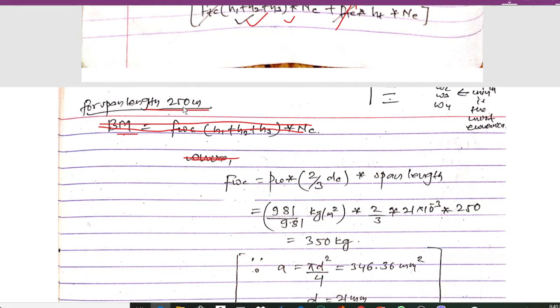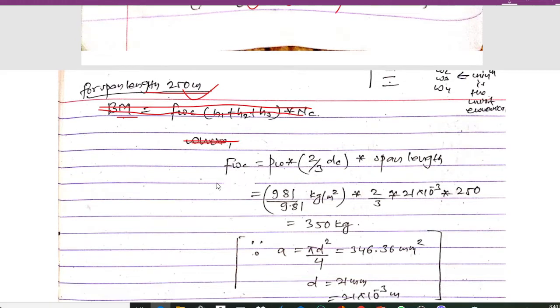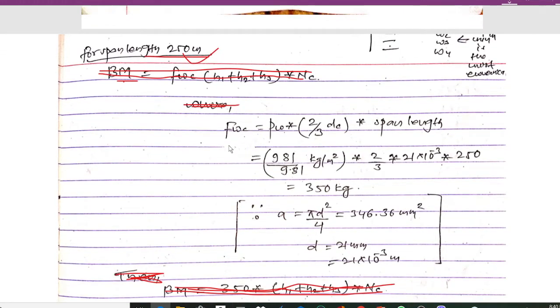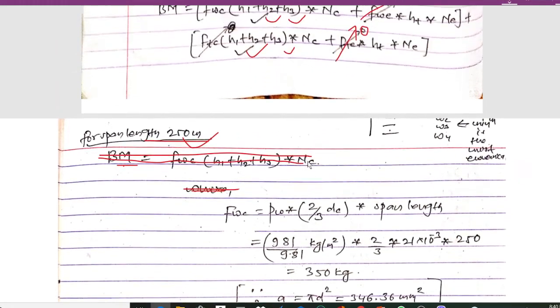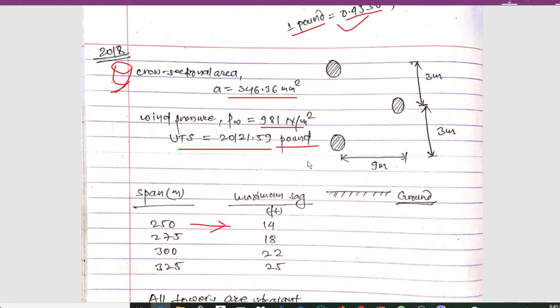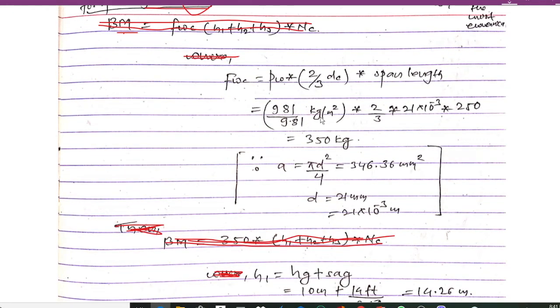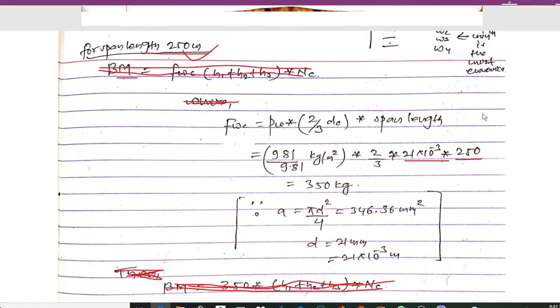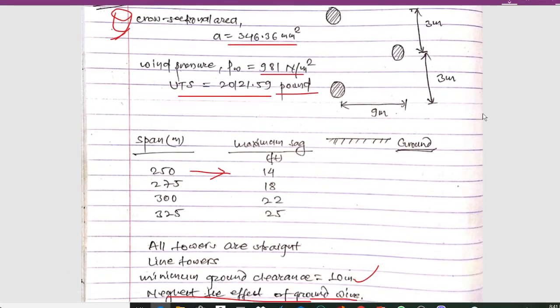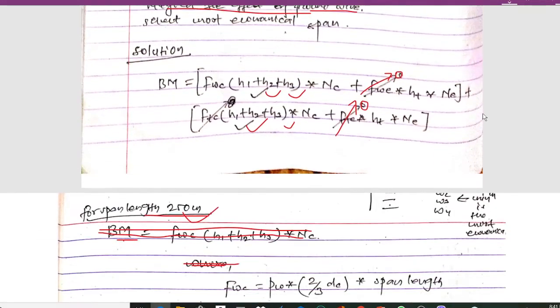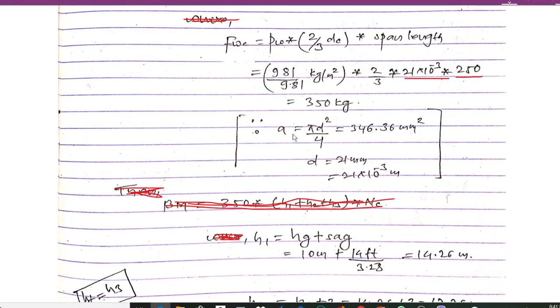For a span length of 250 meters, we first calculate Fwc, the force due to conductors. The formula is Fw = Pw × (2/3) × dc × span length. Pw is given as 981 Newton per meter square; dividing by 9.81 gives kg per meter square. The value of dc is 21 × 10⁻³ meters, derived from the given cross-section area, and span length is 250 meters.